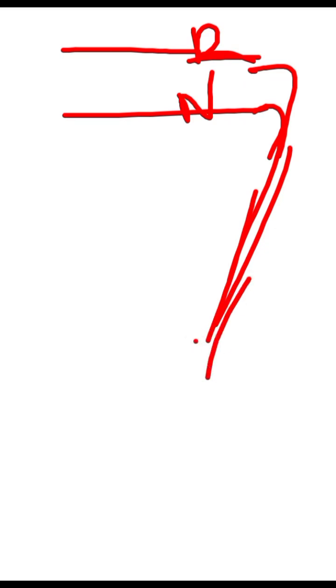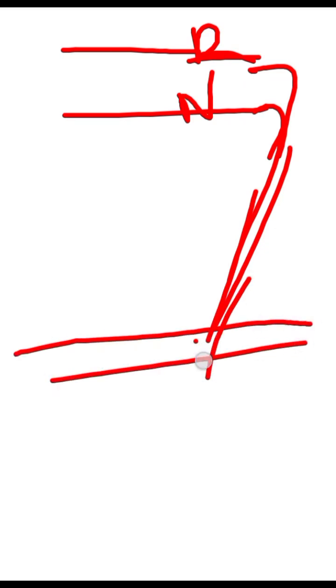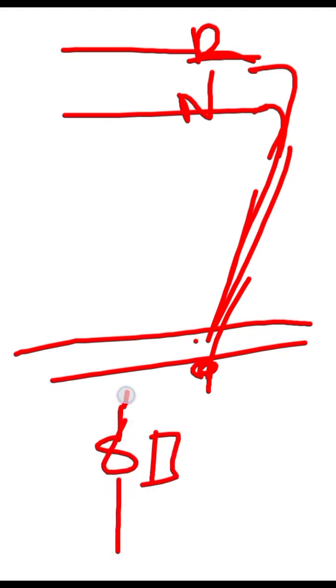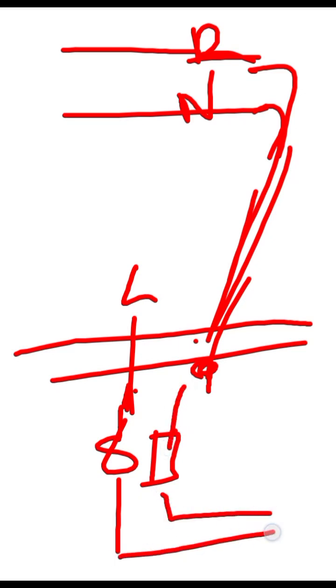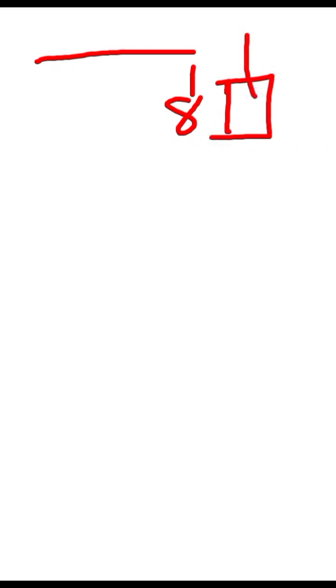At the consumer house, we're going to have a cutout, a neutral link. So the live is going to be taken to the fuse, then the neutral is going to be taken to the neutral link. Then after this cutout, an earthing rod is going to be inserted here, right? So let's see how that proceeds. We have a line wire which passes through the fuse, then we have the neutral link. So an earthing wire is going to be created from this place and is going to be grounded from there.